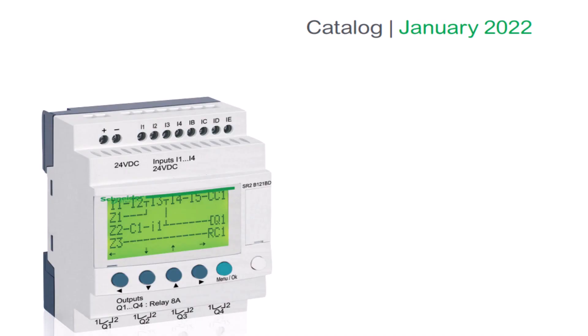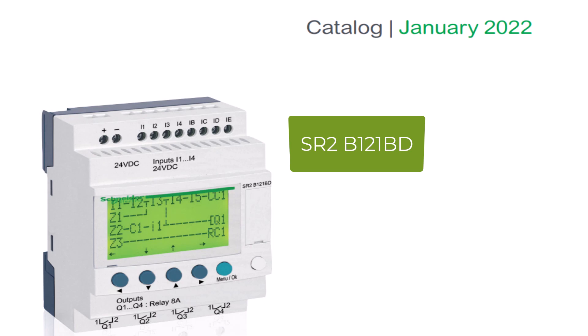In order to connect a two-wire temperature sensor to the Schneider Electric Zelio smart relay, you have to use a 24 volt DC unit. I have the January 2022 catalog open and I'm going to select the SR2-B121BD part number. That is a 24 volt DC unit.